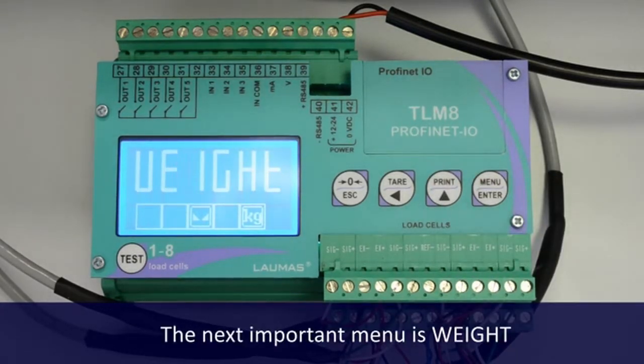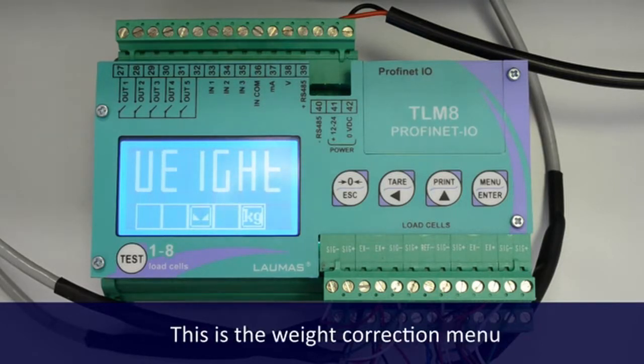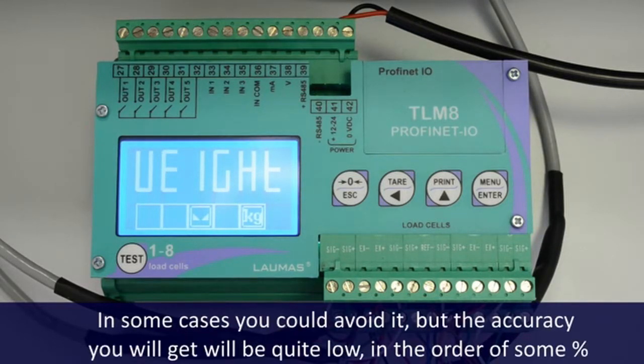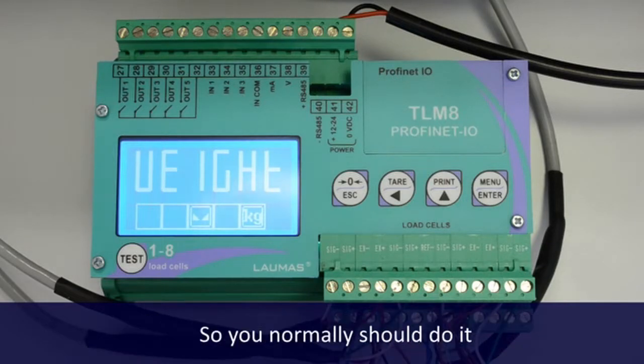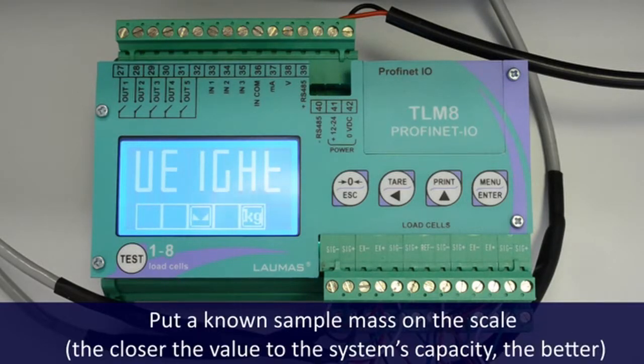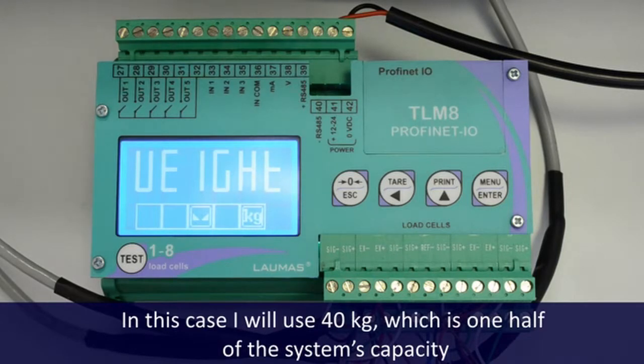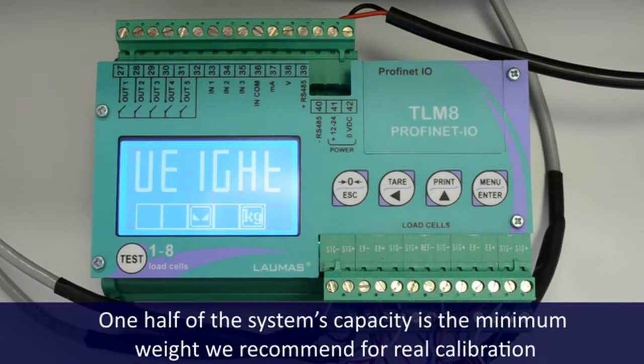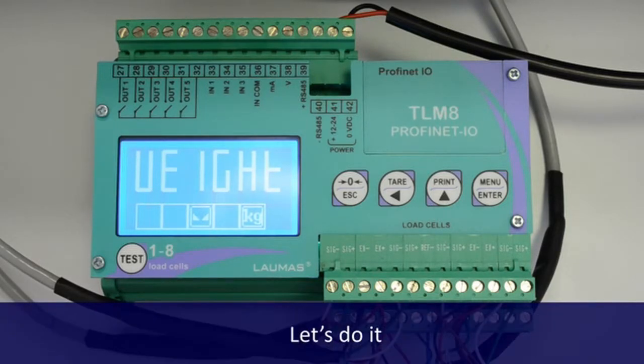The next important menu is weight. This is the weight correction menu. In some cases you could avoid it, but the accuracy you will get will be quite low, in the order of some %. So you normally should do it. Put a known sample mass on the scale. The closer the value to the system's capacity, the better. In this case, I will use 40 kilograms, which is 1/2 of the system's capacity. 1/2 of the system capacity is the minimum weight we recommend for real calibration. Let's do it.